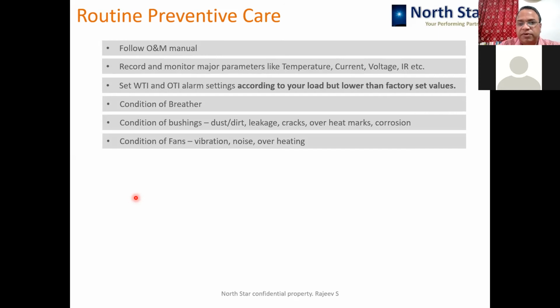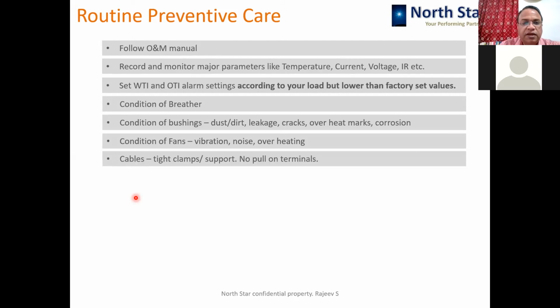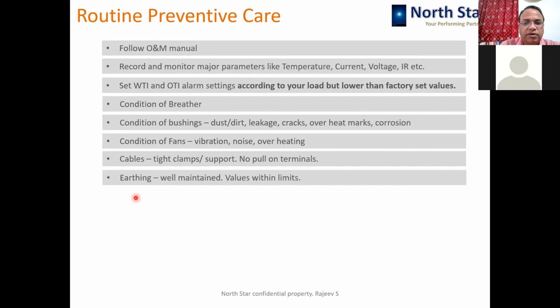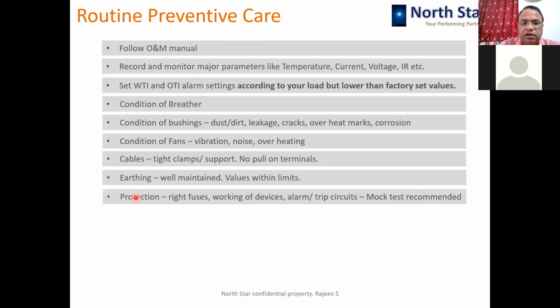Condition of fans for vibration, noise, and overheating. Recently, we are facing a problem at some sites that water is going inside the fans because of some manufacturing defect. So in long service also, water can go in the terminal box and your fans can fail. So that also should be taken care of. Cables: tight clamps, support, no excessive tension on the cables. Earthing, we all know it is to be maintained. Then all protection devices, protection circuits, protection components to be kept with the right fuses. They should be in working condition. Alarm and trip circuits: from time to time a mock test or dry test to be done.